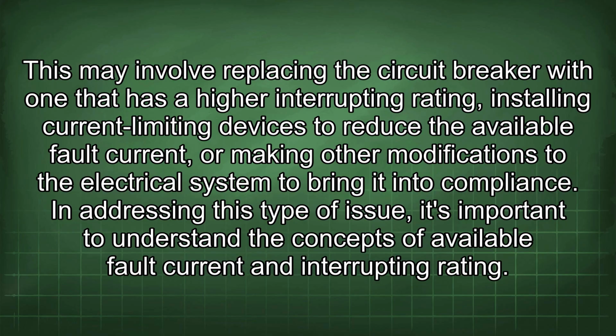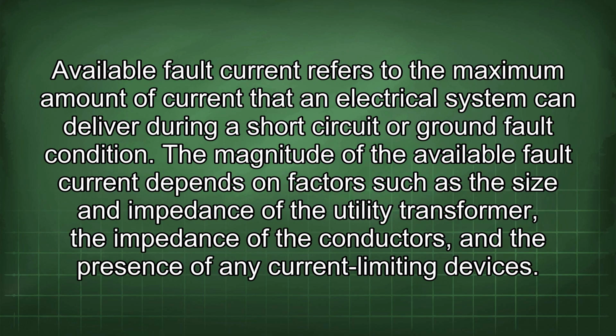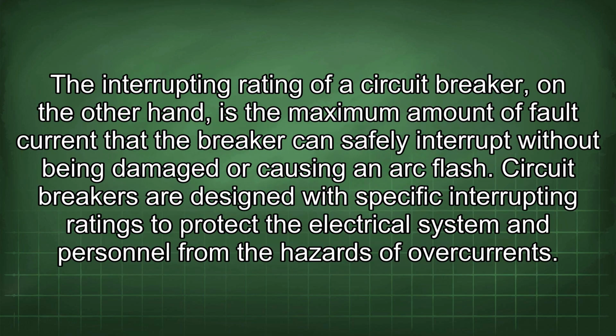In addressing this type of issue, it's important to understand the concepts of available fault current and interrupting rating. Available fault current refers to the maximum amount of current that an electrical system can deliver during a short circuit or ground fault condition. The magnitude of the available fault current depends on factors such as the size and impedance of the utility transformer, the impedance of the conductors, and the presence of any current limiting devices. The interrupting rating of a circuit breaker, on the other hand, is the maximum amount of fault current that the breaker can safely interrupt without being damaged or causing an arc flash.